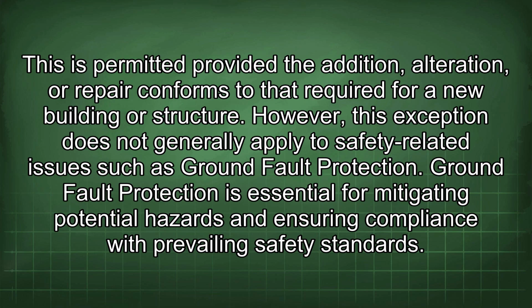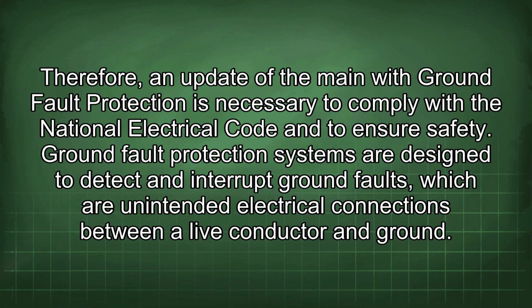Ground fault protection is essential for mitigating potential hazards and ensuring compliance with prevailing safety standards. Therefore, an update of the main with ground fault protection is necessary to comply with the National Electrical Code and to ensure safety. Ground fault protection systems are designed to detect and interrupt ground faults, which are unintended electrical connections between a live conductor and ground.